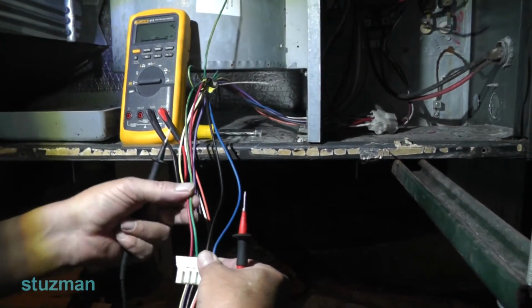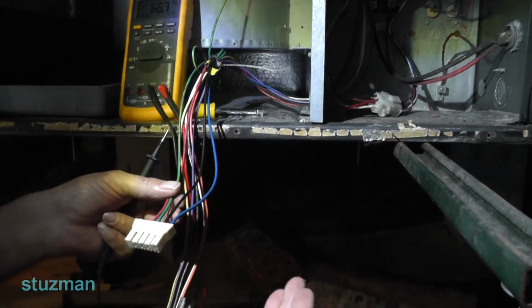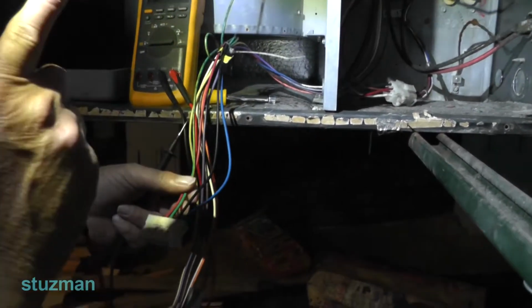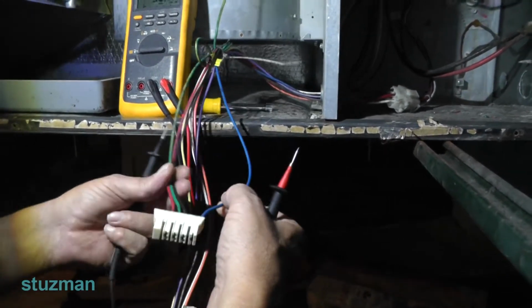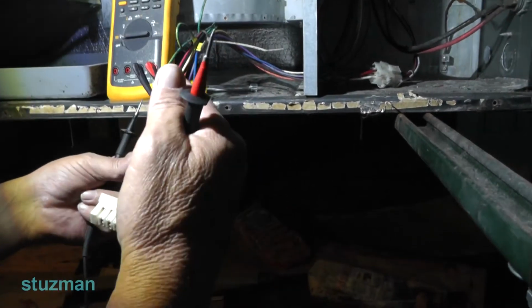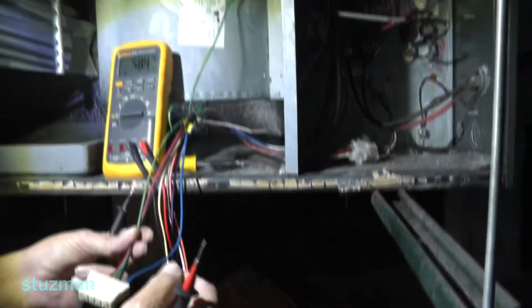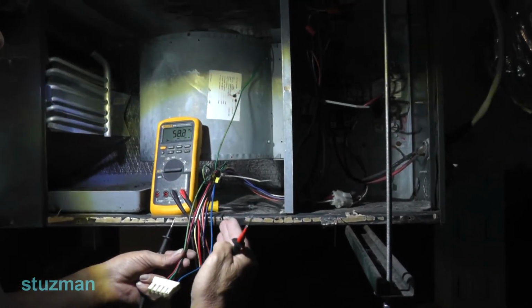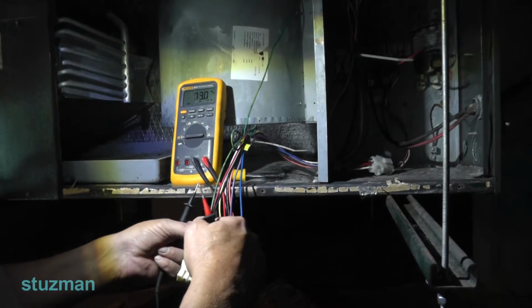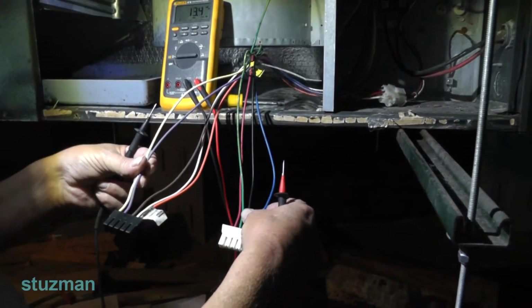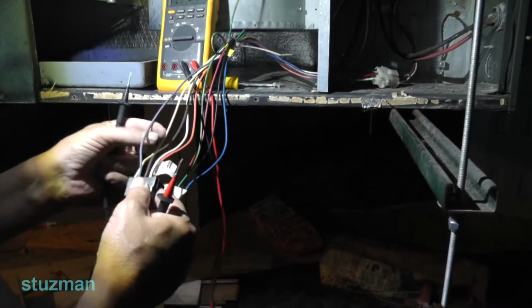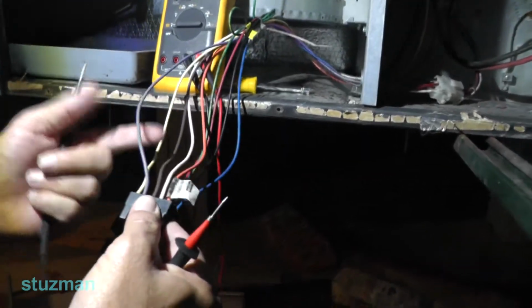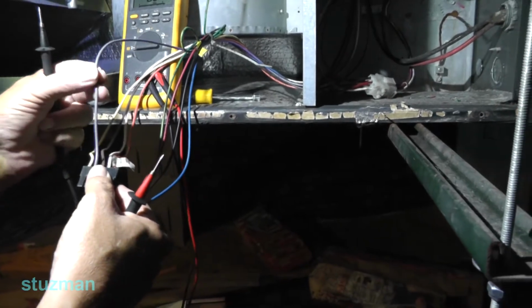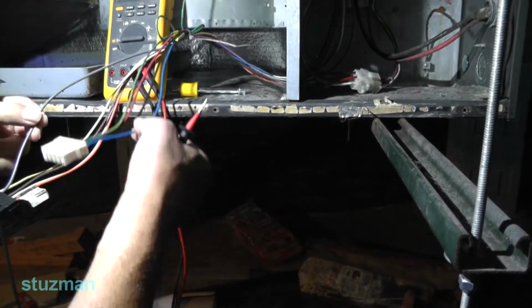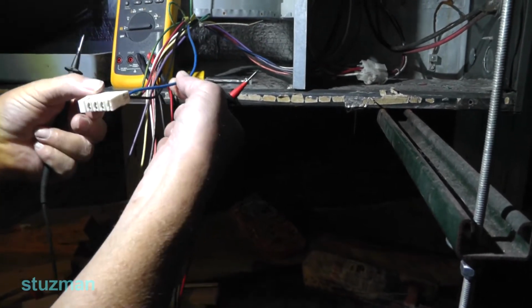Now for the communication, they take the 24 volts AC. In my case, I only have one tap that's being used. Remember, the manufacturer can program this electronic control board up here for multiple taps, depending on if it's got a cooling cycle, the heat cycle, single stage, dual stage. So they can program all of these taps if they want to. But in my case, I only have one. The one that's being used is this purple wire. So between this purple wire, there's my 24 volt AC, and the other side, they put it over on the line power plug, which is going to be this blue wire.